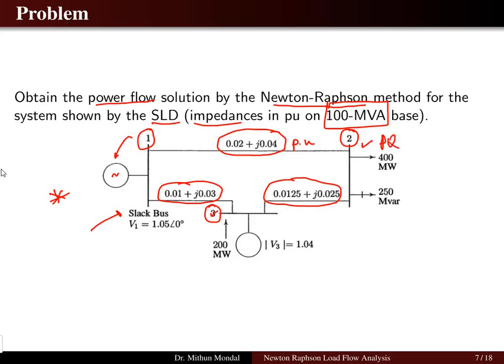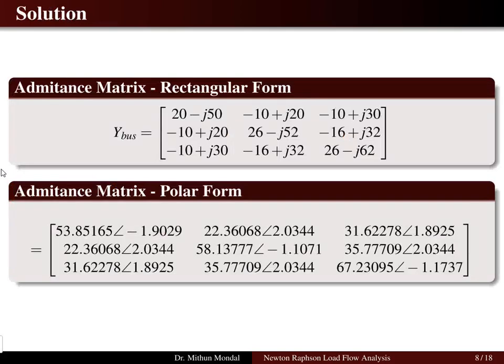Bus 3 has power delivered, so it is also a generator bus. One generator bus must be treated as the slack bus. Out of buses 1 and 3, one is designated the slack bus. In this problem, bus 1 is the slack bus with voltage magnitude 1.05 per unit and angle 0. Let us now solve this problem using Newton-Raphson.